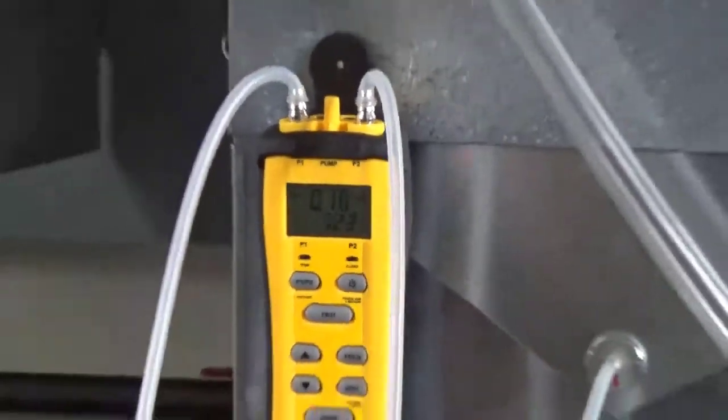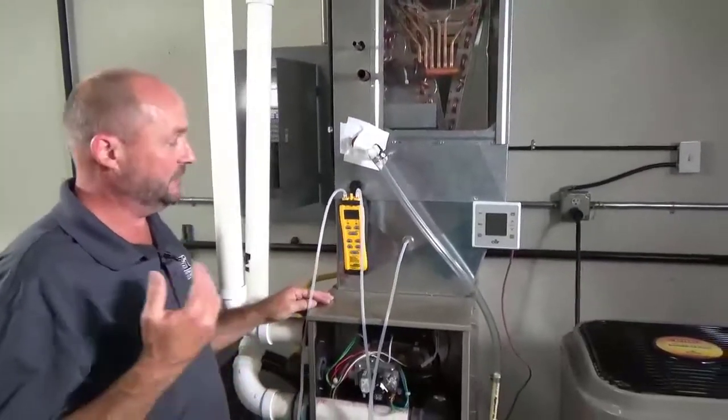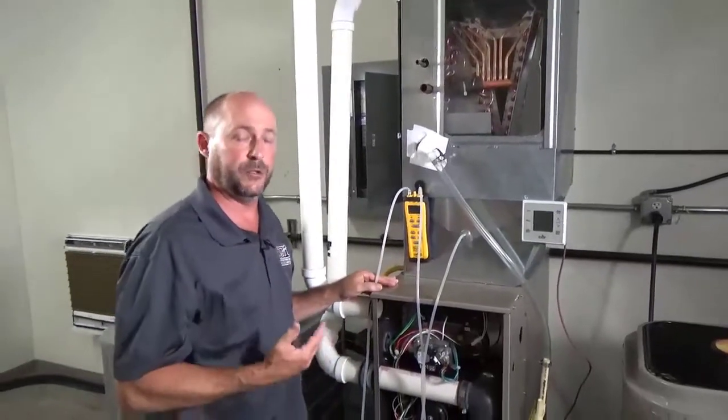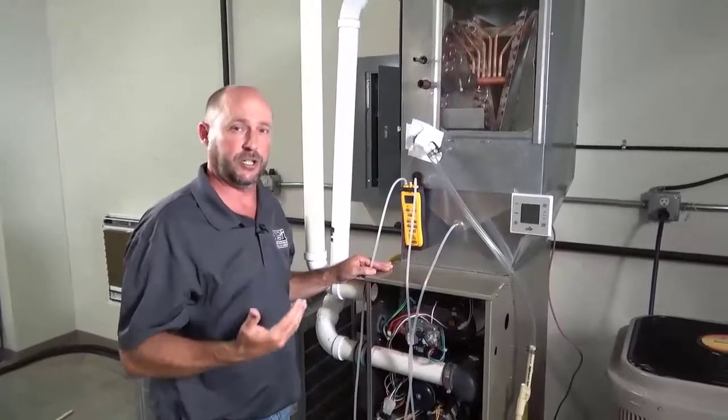So that's the way once you get your total external static pressure you can go to your blower chart and check out your CFM and make sure you're setting up your CFM to the proper amount going for whatever ton of air conditioning you have.